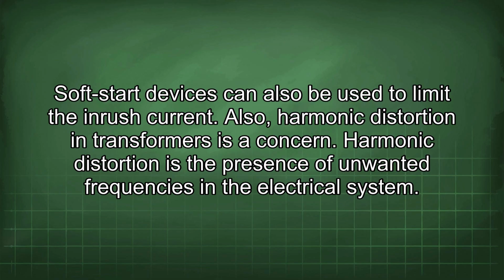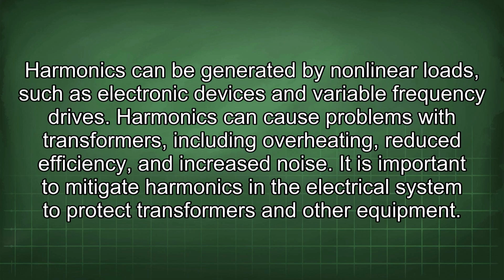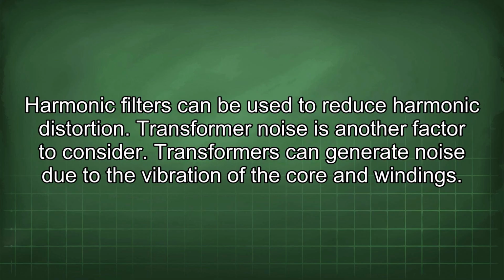Also, harmonic distortion in transformers is a concern. Harmonic distortion is the presence of unwanted frequencies in the electrical system. Harmonics can be generated by nonlinear loads such as electronic devices and variable frequency drives. Harmonics can cause problems with transformers, including overheating, reduced efficiency, and increased noise. It is important to mitigate harmonics in the electrical system to protect transformers and other equipment. Harmonic filters can be used to reduce harmonic distortion.